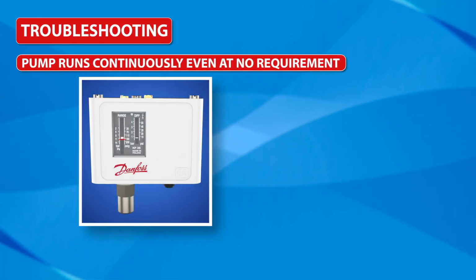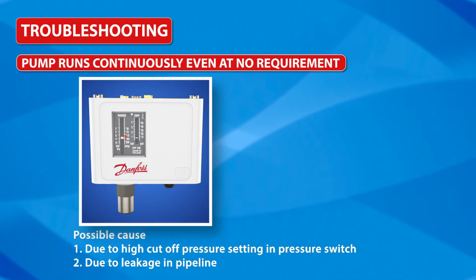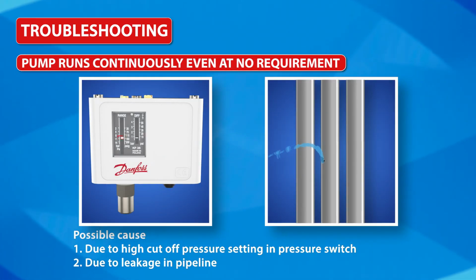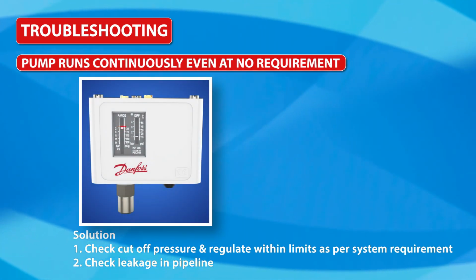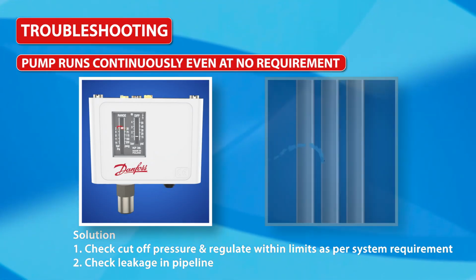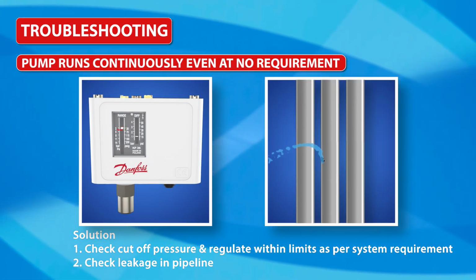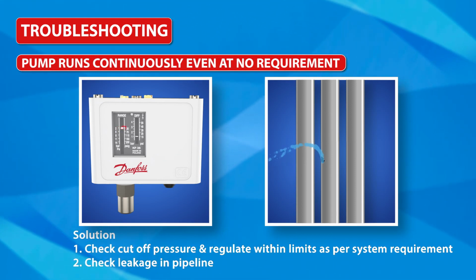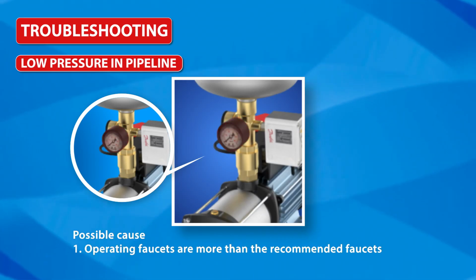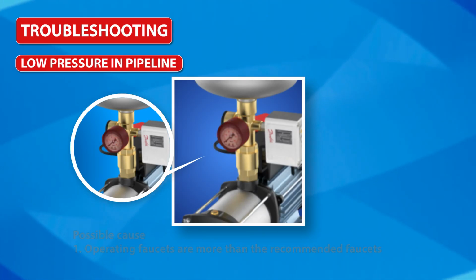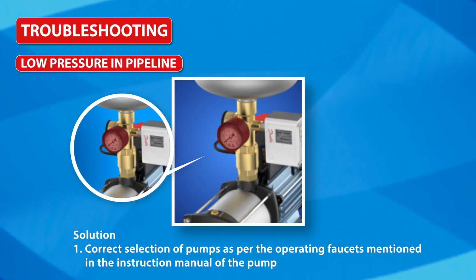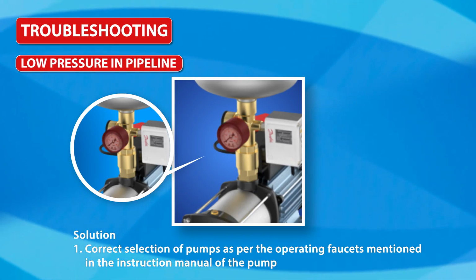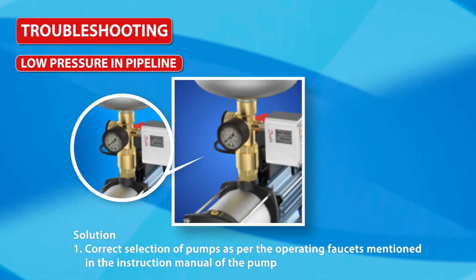Troubleshooting: if the pump runs continuously even when there is no requirement. Possible cause: first, high cut-off pressure setting in the pressure switch. Second, leakage in the pipeline. Solution: first, check cut-off pressure and regulate within limits as per system requirement. Second, check for leakage in the pipeline. Low pressure in pipeline. Possible cause: operating faucets are more than the recommended faucets. Solution: correct selection of pumps as per the operating faucets mentioned in the instruction manual of the pump.